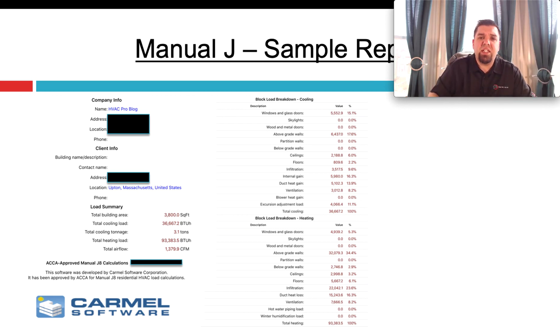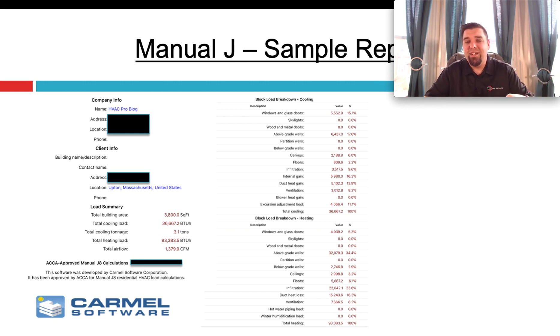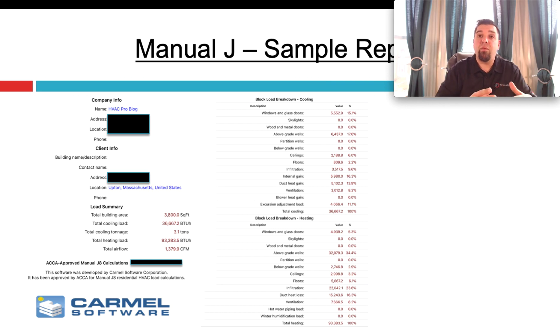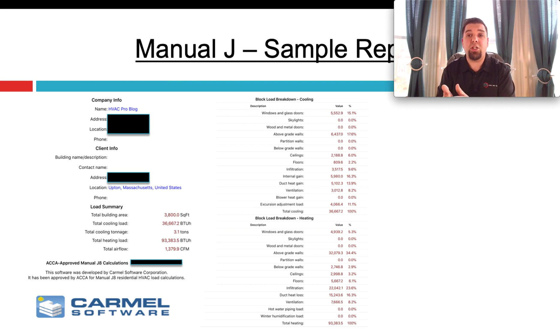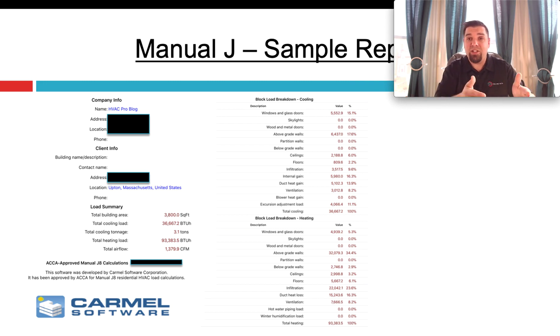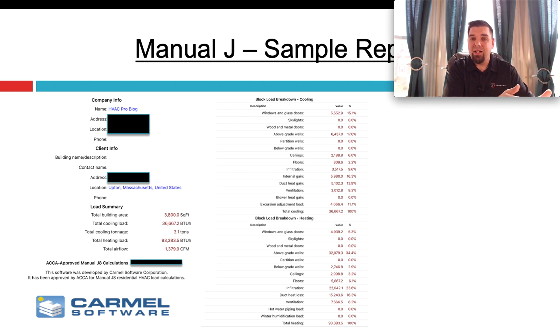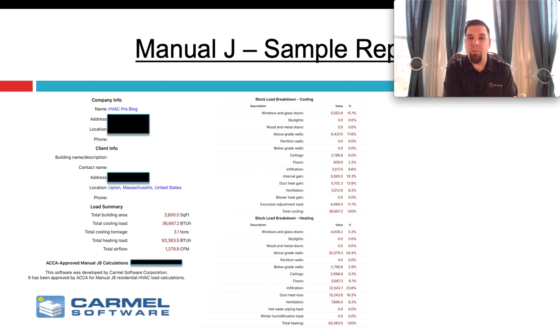Also check things like partition walls — for example, if the space borders a garage, which is unconditioned even though it's not outdoors, you need to account for that partition wall. I have zero for partition walls because I don't have a garage or unconditioned spaces. Take a look at ceilings, floors, and infiltration — all the things we talked about in the site survey form. On the heating side, you can see I need about a three-ton system for cooling and somewhere around 90,000 BTUs for heating. I've changed the leakage settings and it didn't significantly change equipment size, as we discussed — though drastically misrepresenting it, like calling it tight when it's really semi-loose, could change the result significantly.